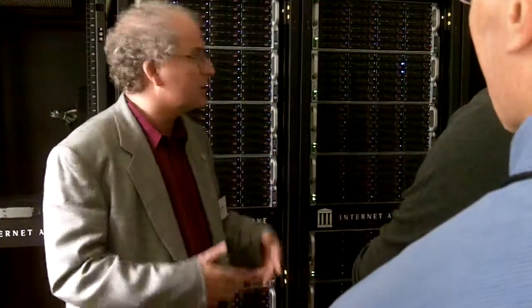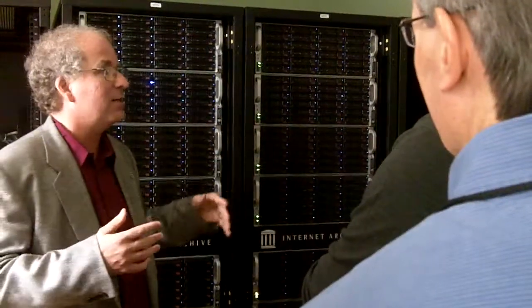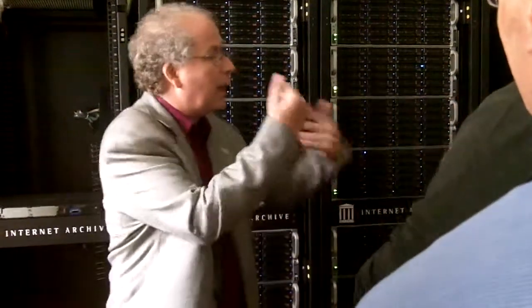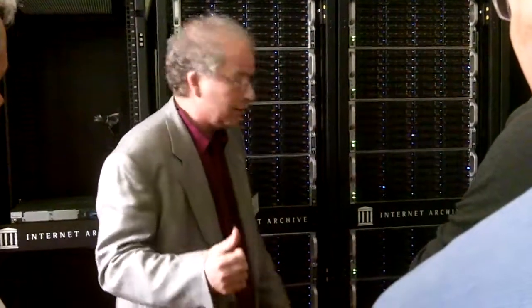These machines are basically designed for office environments, with all these hard drives and motherboards. As long as the input air is like an office environment, you're in good shape. Most data centers have real problems not having some places at 90 degrees, and they have all this air conditioning. So why not just open the doors and windows more? It's just not where that culture came from. But it saves you between 30% and 50% on your power cost, and a lot in capital costs, power, and facilities expense.